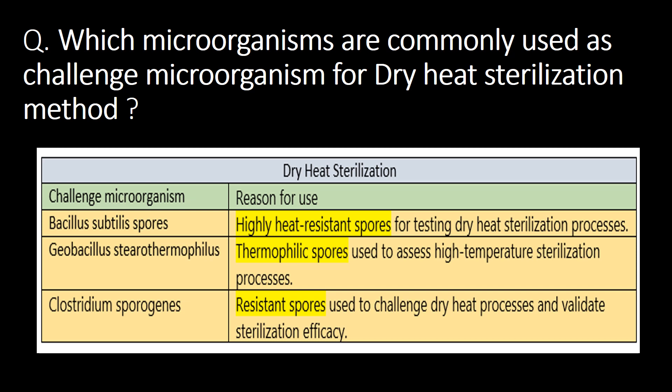Which microorganisms are commonly used as challenge microorganisms for dry heat sterilization? In the pharmaceutical industry, dry heat sterilization is commonly used in depyrogenation tunnels and depyrogenation ovens. Refer to the table below for commonly used challenge microorganisms. These are Bacillus subtilis spores, Geobacillus stearothermophilus, and Clostridium sporogenes. The common reason for selecting them is their property of being highly heat-resistant spores.